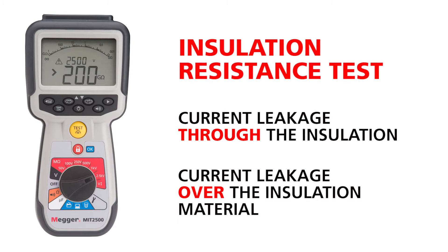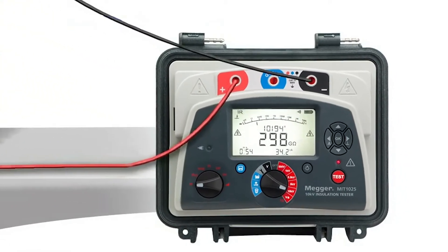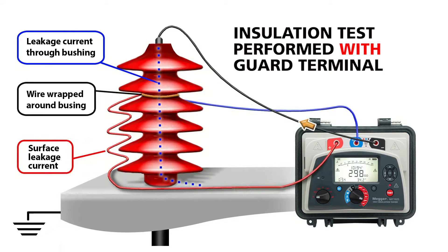Many of the Megger insulation testers feature a guard terminal, such as the MIT1025-10KV model as shown here. The current leaking through the insulation without the surface leakage is the true measure of the safety and quality of the conductors and insulation you're testing. The Megger MIT2500 is the only handheld megohmmeter with a guard terminal, which eliminates or greatly reduces the effect of surface leakage on the test results.